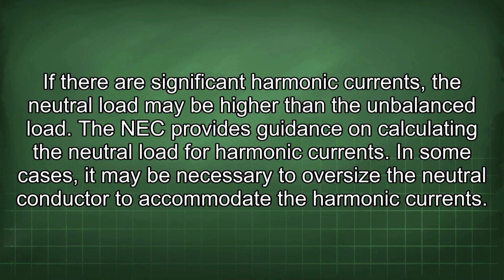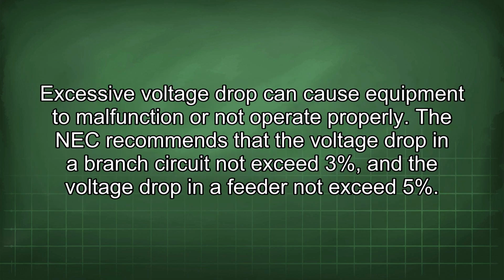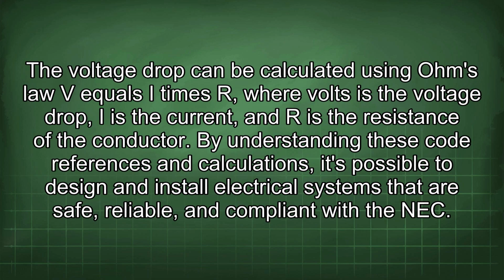When calculating the neutral load for a service or feeder, it's important to consider the unbalanced load and any harmonic currents. The unbalanced load is the difference between the current on the phase conductors and the neutral conductor. If there are significant harmonic currents, the neutral load may be higher than the unbalanced load. The NEC provides guidance on calculating the neutral load for harmonic currents. In some cases, it may be necessary to oversize the neutral conductor to accommodate the harmonic current.